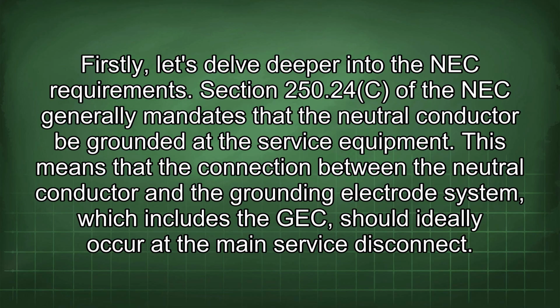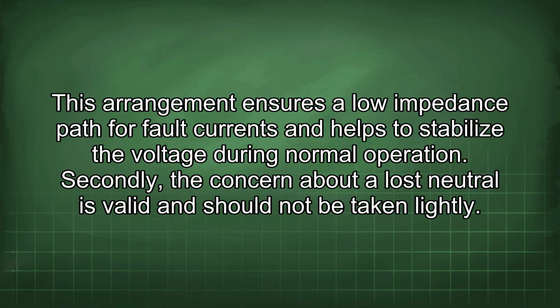Firstly, let's delve deeper into the NEC requirements. Section 250.24(C) of the NEC generally mandates that the neutral conductor be grounded to the service equipment. This means that the connection between the neutral conductor and the grounding electrode system, which includes the GEC, should ideally occur at the main service disconnect. This arrangement ensures a lower impedance path for fault currents and helps to stabilize the voltage during normal operation.